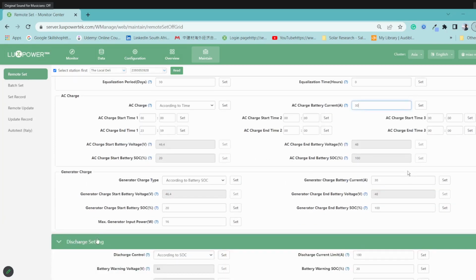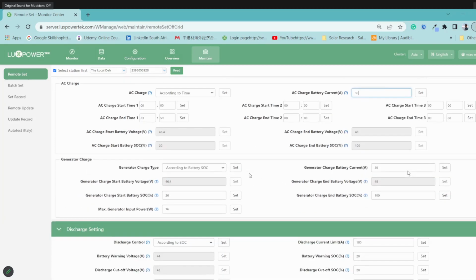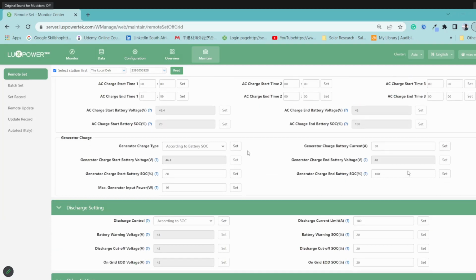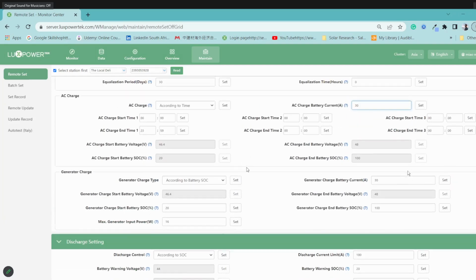Okay. The generator side. So from the generator, our SMA 5000 is quite sensitive, as the power coming from the generator can sometimes not be very stable. I know Johan has a lot of information on this. You can also vouch for that. So what we do is for SMA, we recommend not going above 50% of the generator's capacity. So if let's say you guys have a 3 kilowatt Jenny or 4 kilowatt Jenny or 4.5, just go half the power and program it inside the year.